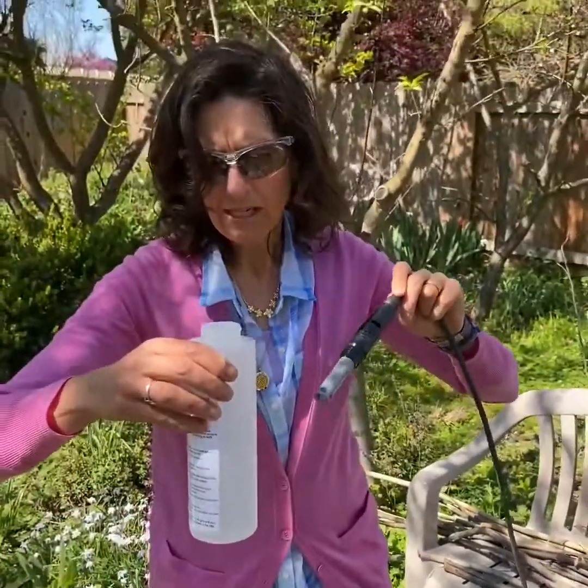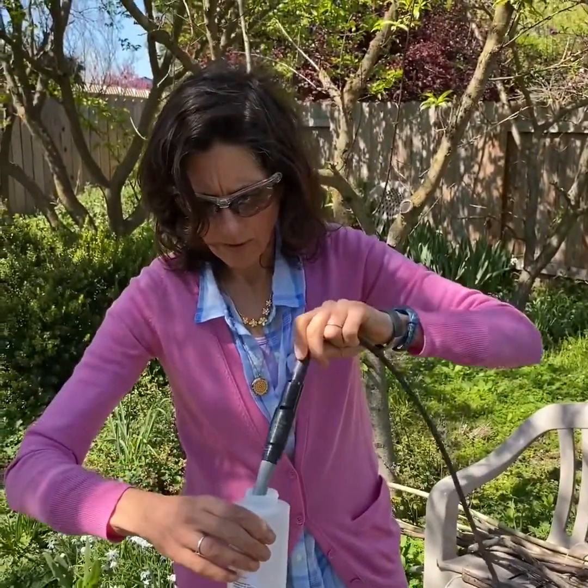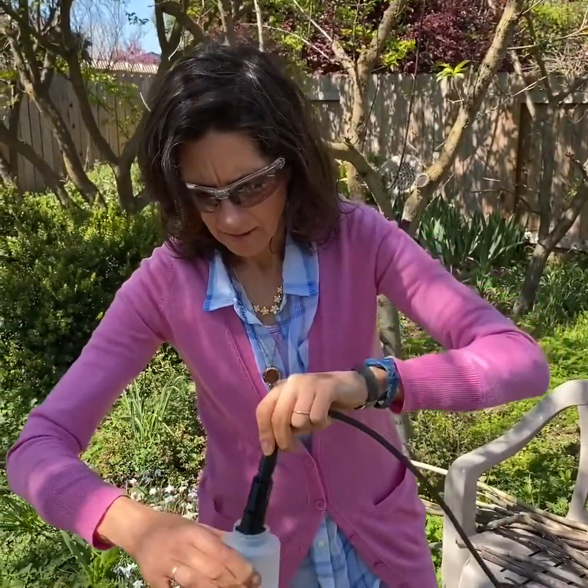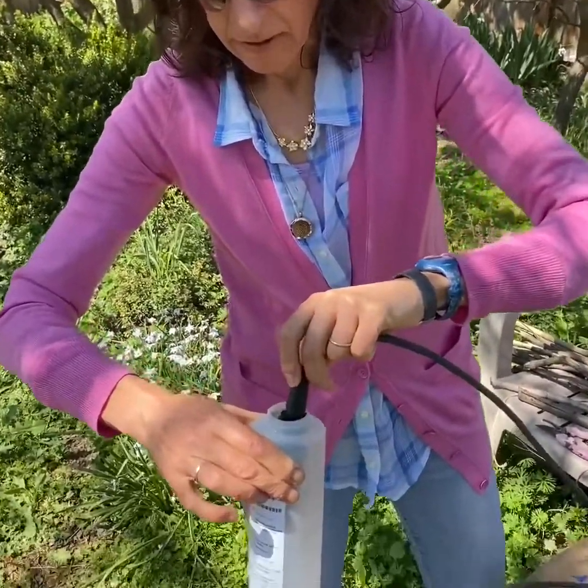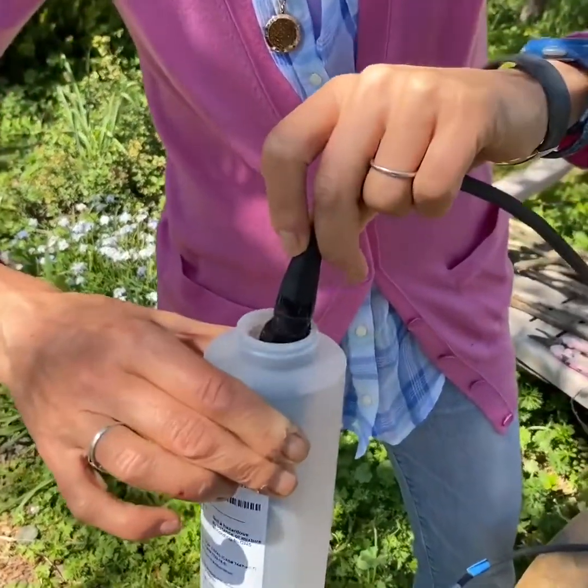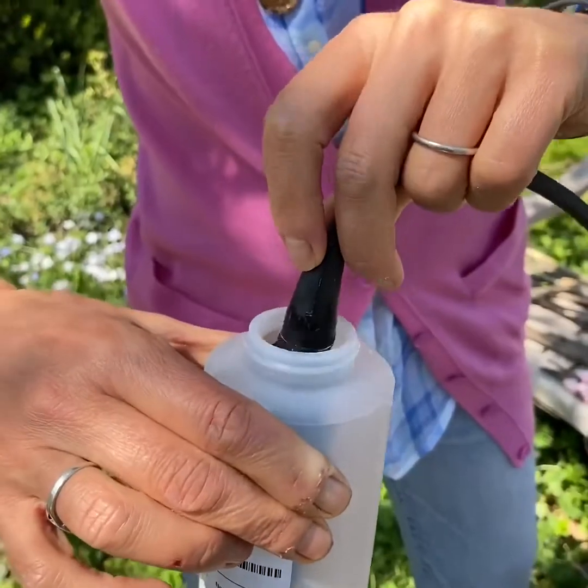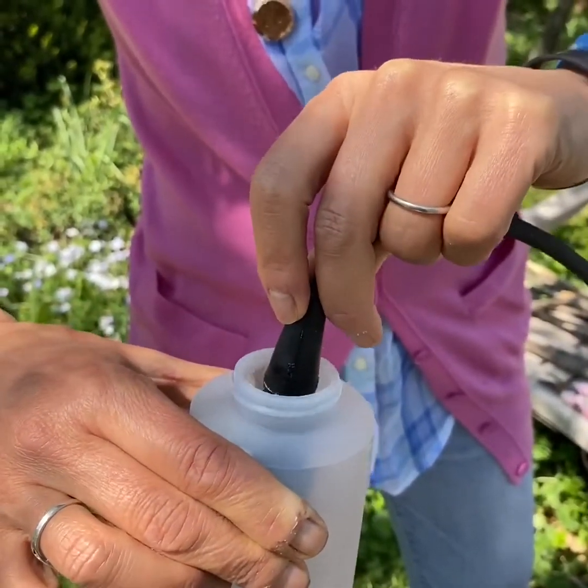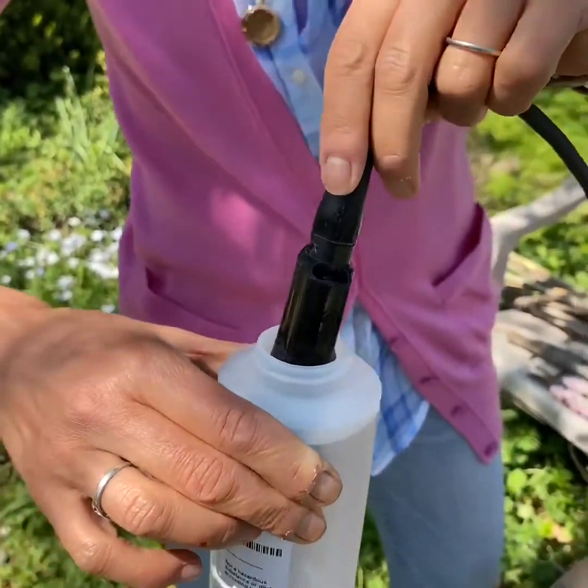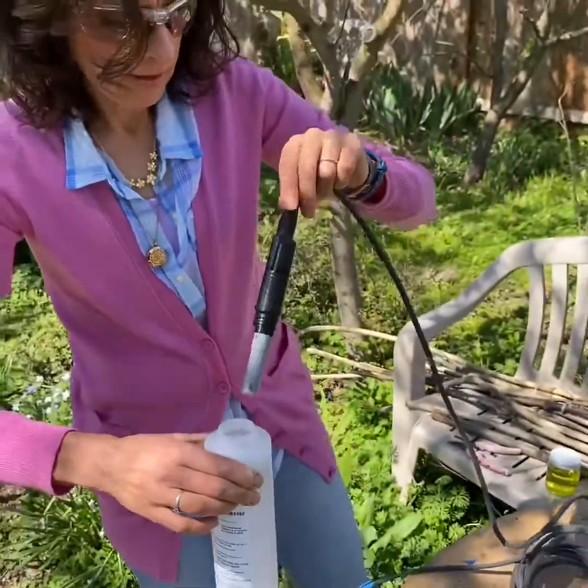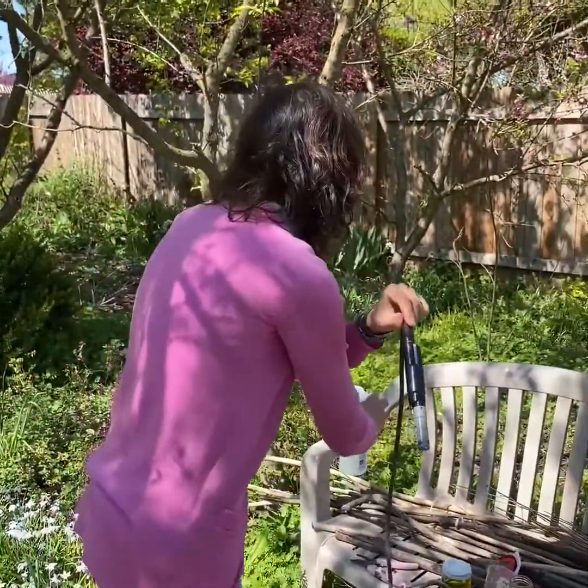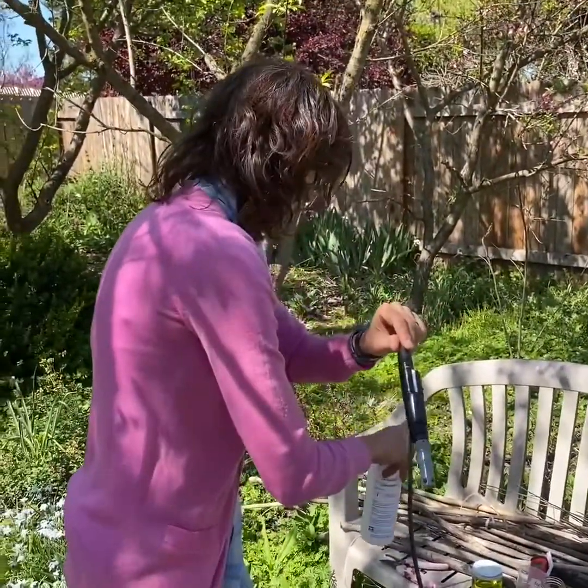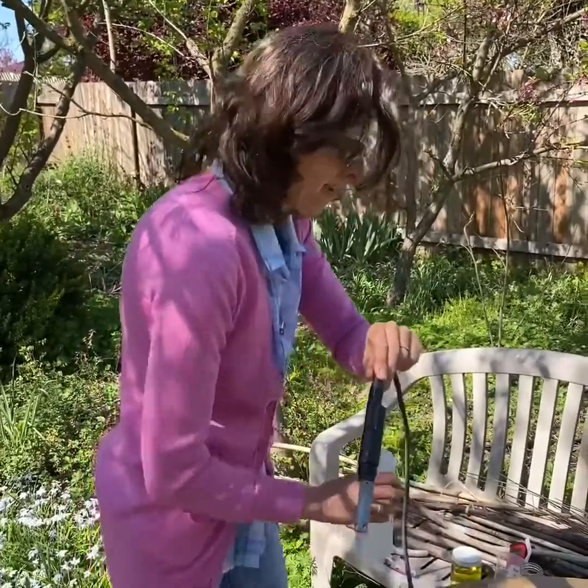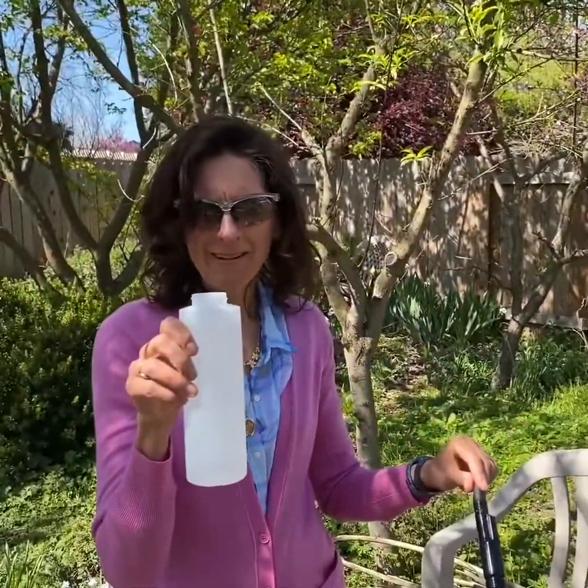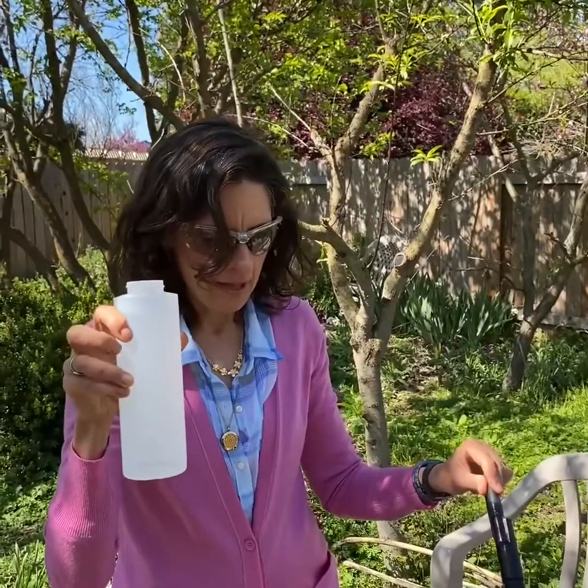So I'm going to stick it into the rinse bottle. It's going to water my yard a little bit. And I'm just going to set it in there for a little bit, rinse it out, let it rinse. And then I'm going to take it out, and I'm going to switch out my bottle and get my calibration bottle. And so this is the calibration solution.